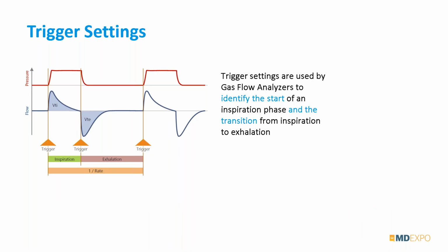And then depending on the mode of your ventilator, your flow might do something like this. It's going to rise, deliver an inspiratory tidal volume, and then in exhalation you will see some air coming back from the patient, or the test lung in our test setup, maybe back to the ventilator. Now one task of our gas flow analyzer is to measure different parameters based on the timing of these waveforms. We call them breath-based parameters. To do so, the analyzer needs to know what is an inspiration phase and what is an exhalation phase, okay? Somehow the test equipment must know, okay, now an inspiration starts and now it changes to exhalation, and then at some point the next inspiration phase starts.